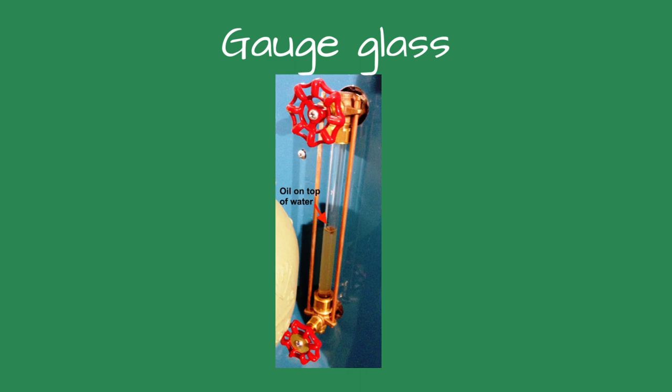The oil was typically from the pipe threading done when installing the boiler. This is why the manufacturer suggests cleaning steam boilers after installation. There was oil and solids on top of the water.